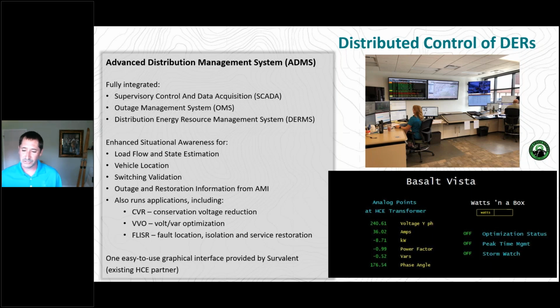The third mode we got into was storm watch, taken directly from the Lake Christine fire. We want to push as much energy as we can into the system in response to an outage. This could be a scheduled outage, where linemen are going out to change a transformer, or it could be in anticipation of snow load, where we just want to push as much energy as we can into the house, into the batteries, into the EVs, into the hot water tank, or preheat the air conditioner or heater a little bit.